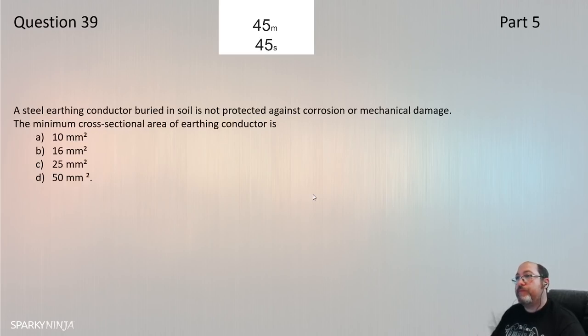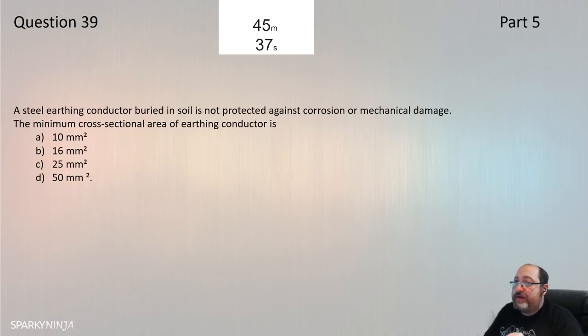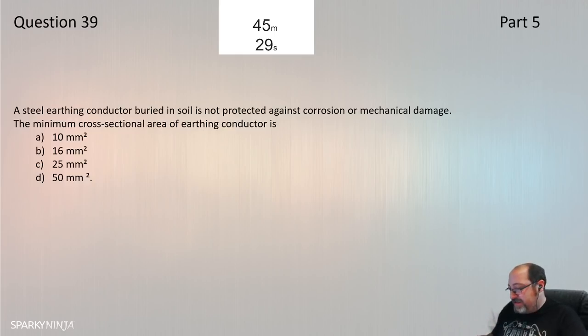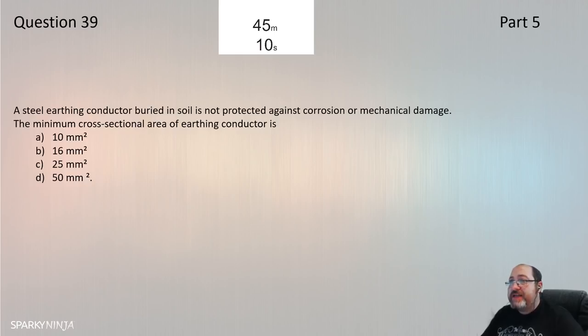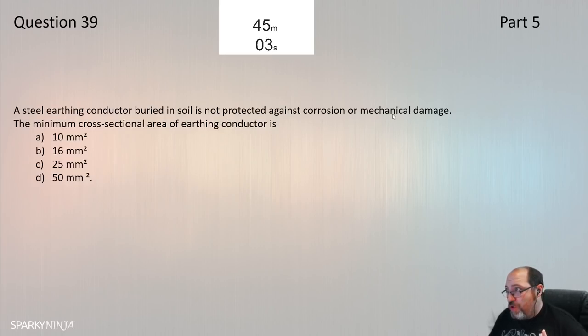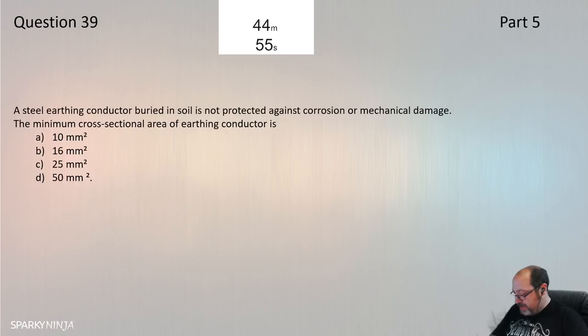Question 39: An earthing conductor buried in soil, not protected against corrosion or mechanical damage — what is the minimum size? This relates to Chapter 54, Table 54.1 — minimum cross-sectional area of buried earthing conductors. The conductor is steel, not protected against corrosion or mechanical damage. From Table 54.1: 50mm². Question 39 is D — 50mm².